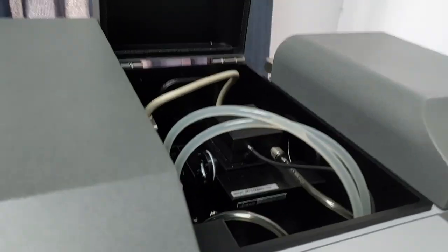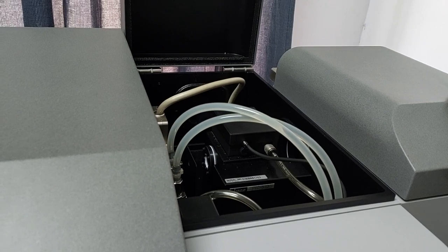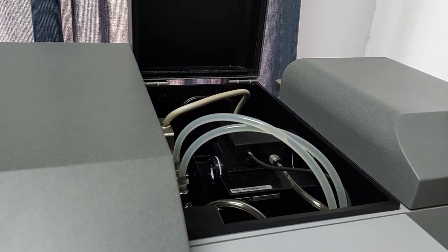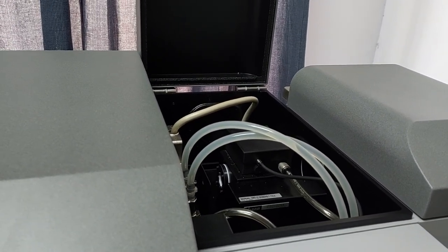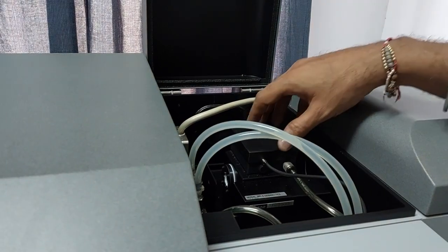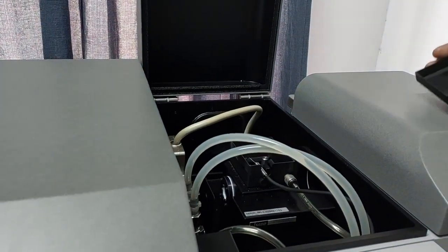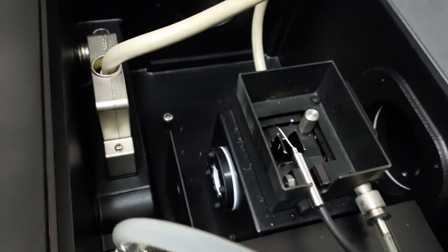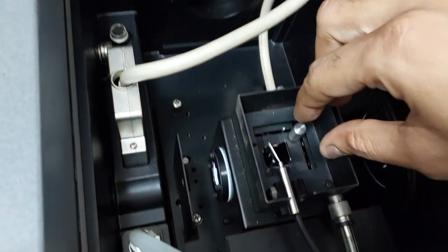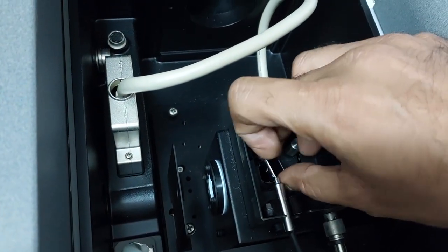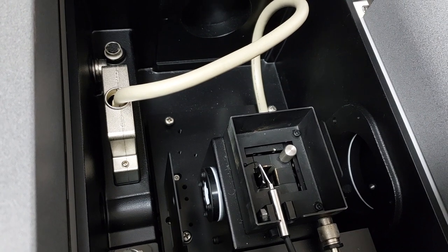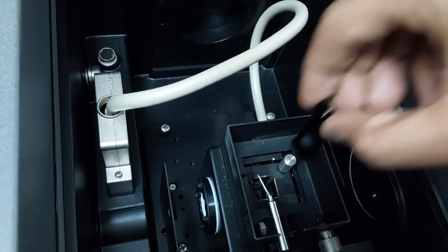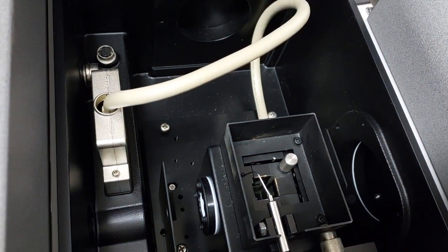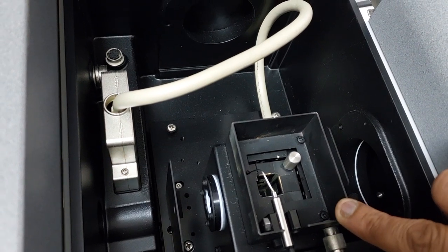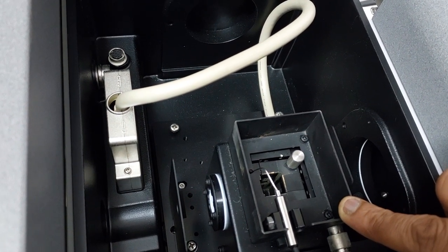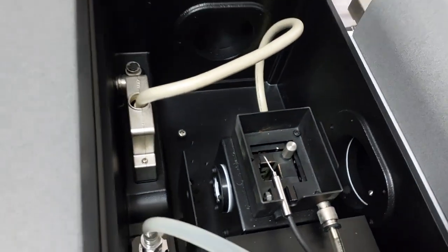The cuvettes used for CD spectroscopy are quartz cuvettes, because you are working in the UV range and glass strongly absorbs the UV radiation, so you need quartz. This is the cuvette chamber. What you are seeing here are the adapters, which I am taking out right now. Once you take out the adapters, you can easily fit a 1 centimeter path length cuvette in this sample chamber.